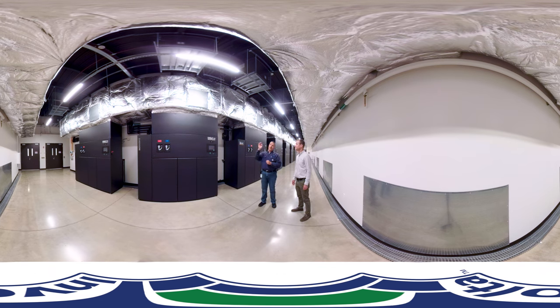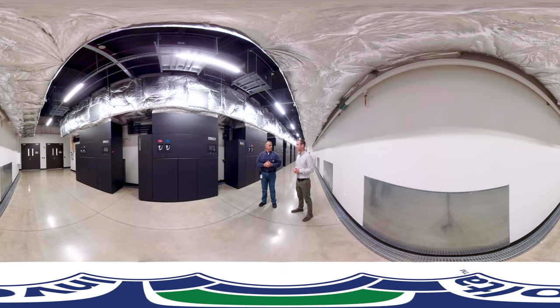Lastly, from a structural protection perspective, we have this overhead fire sprinkler system — but it's not your normal fire sprinkler system that has water in it. It's actually a dual interlock pre-action system, so it has compressed air in it until such time that we'd have a fire event warranting our need to put water in that pipe to protect the structure. Wow, that's really impressive. Tom, we really appreciate your time and thanks for sharing all this with us today. Not a problem — you have yourself a great day.